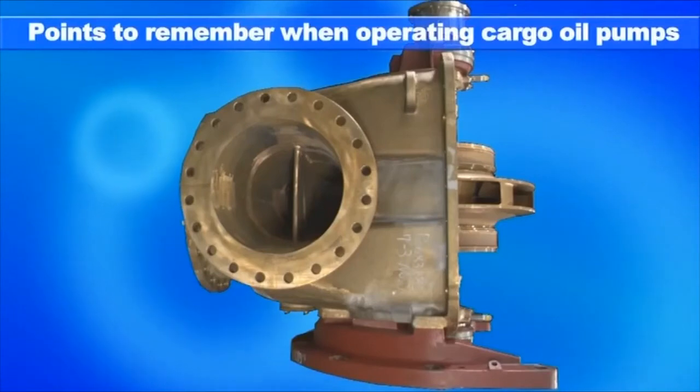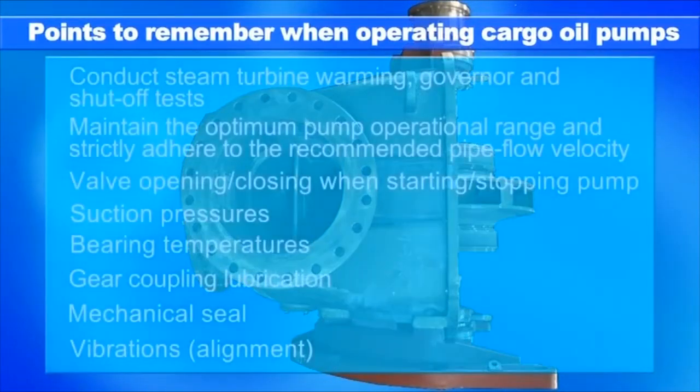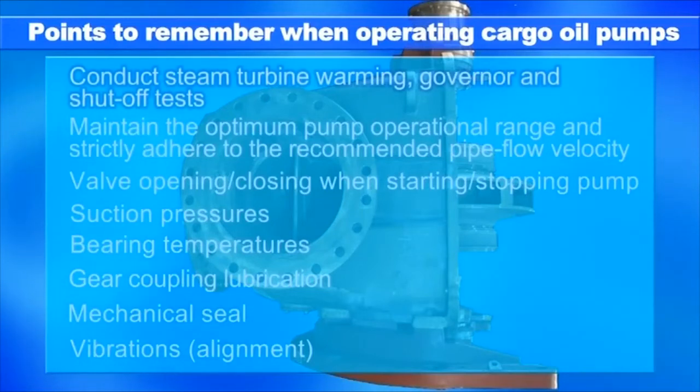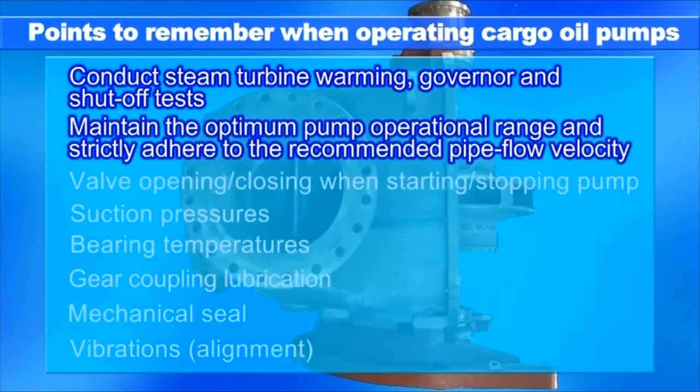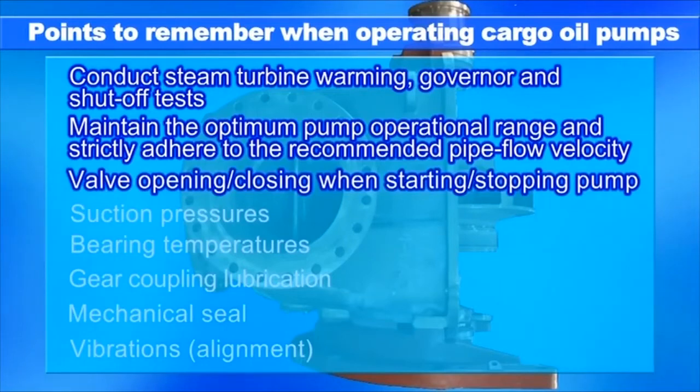The following precautions must be taken to operate and maintain cargo oil pumps: conduct steam turbine warming, governor, and shut-off tests, maintain the optimum pump operational range and strictly adhere to the recommended pipe flow velocity, never open or close valves abruptly when starting or stopping the pumps, and prevent suction pressures from falling.